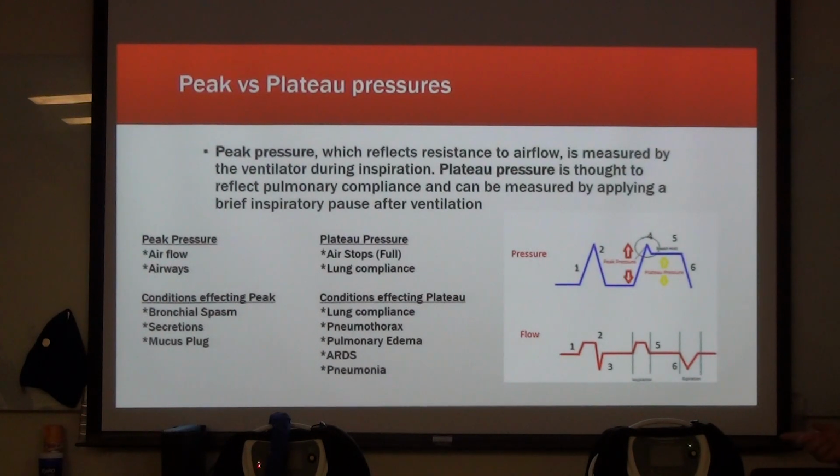But thinking about this, we've got them on CPAP pressure support. We're getting ready to do that, and then all of a sudden the patient stops breathing. You're in the process of doing your thing. You hear beep, beep, beep. You look over and see the apnea alarm flashing, and you look down and see the mode change from your CPAP pressure support to assist control. What just happened?